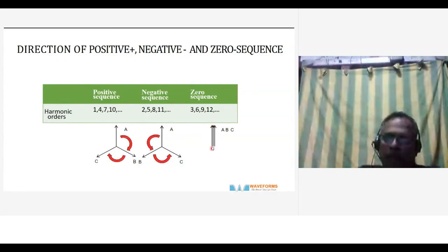So suppose there are 10 amps of third harmonic current. What happens is each phase has 10 amps, 10 amps, so there is about 30 amps of this third harmonic current in the neutral, and they sum up at the neutral or add to the neutral. They are additive to the neutral. So this is the issue with the third harmonic and unbalanced flow.